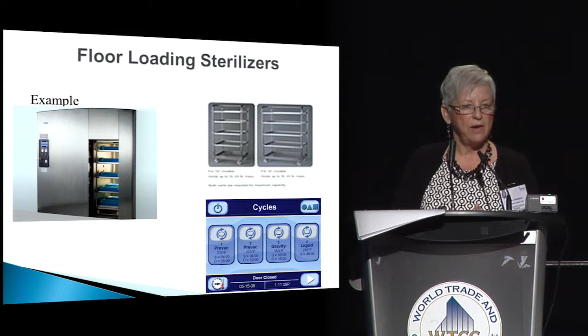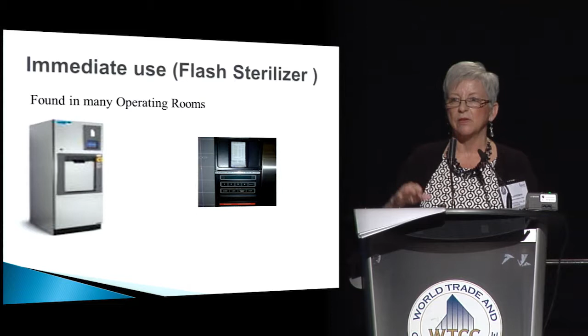The next one is the immediate use flash sterilizer, and this is found in most operating rooms today. This is a more modern looking one than some of the older ones out there. This one actually has a printer, and printer capability for any sterilizer is so important, because you want to be able to save that documentation so that if there's an incident or an occurrence within the facility, you can go back and look at what happened in MDR. They might have been having trouble with preventive maintenance, or then again, everything could have been just perfect, and you move on to see if there's an issue with transportation or anything like that.